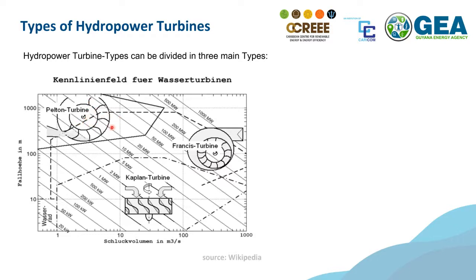On the next level we have the Kaplan turbine. This is made especially for low head, like the river plants you saw before. This is a low head, like 10 meters in the river. Kaplan is very well designed for low head and also high volume. So for a typical large river with a small dam, you need high volumes and low head, so the Kaplan turbine is the best one. Everything depends on the volume and the head, and then you choose the turbine.